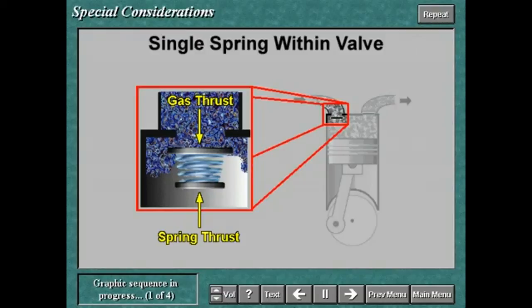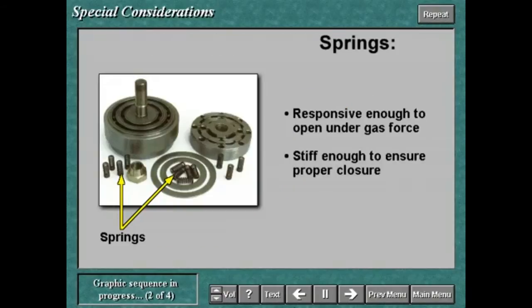If spring stiffness and ring lift or gas velocity are not correctly related to each other, the rings are not stable and will flutter. Springs must be selected so that they are responsive enough to allow the rings to open under the gas force and to avoid vibration. They must also be selected so that they are stiff enough to avoid closure after the dead end of the stroke.